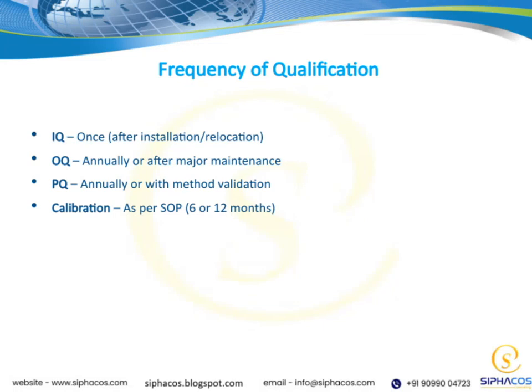Let's talk about the frequency of qualification for different activities. First, IQ, or installation qualification, is typically done once after installation or relocation to ensure everything is set up correctly. Then, we have OQ, or operational qualification, which should be performed annually or after major maintenance to confirm the equipment continues to operate as intended.